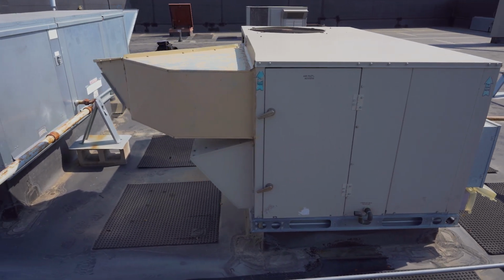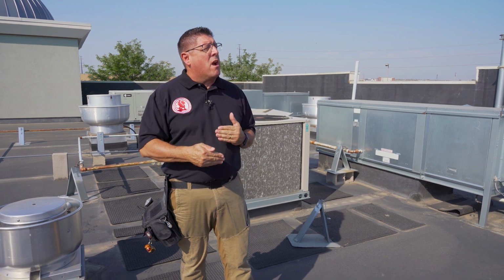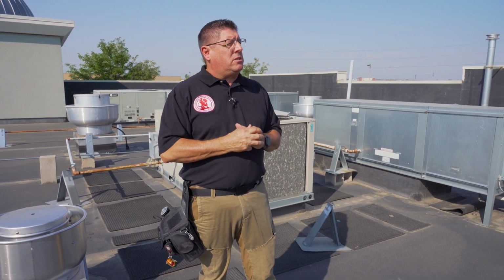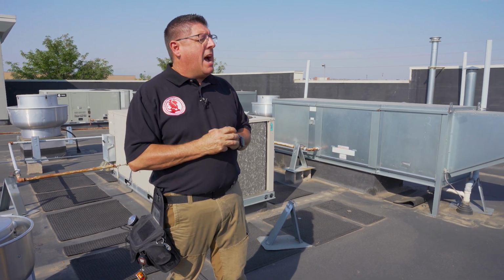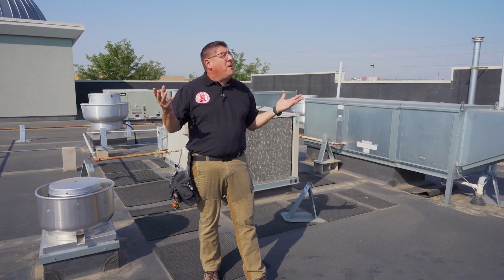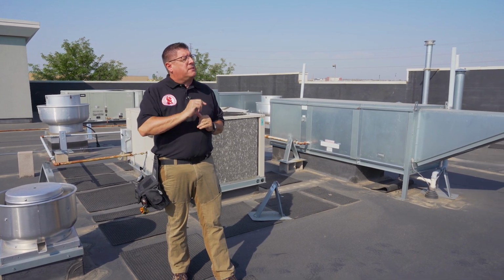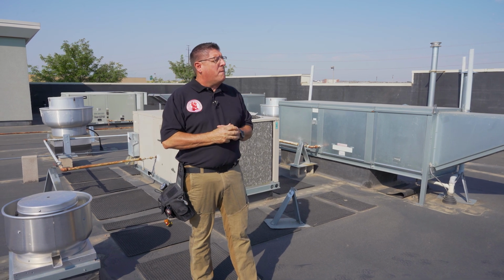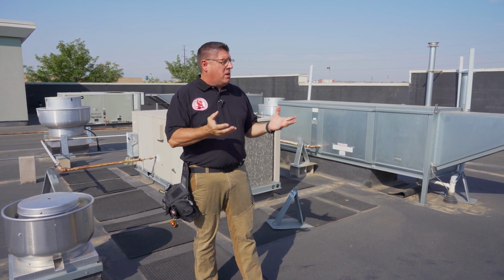These units up here on the roof are obviously not in a confined space, but it is very important when you do your inspections to note that if there are any units in a confined space, while we don't calculate for combustion air, we do need to be aware of the combustion air requirements necessary. Also, on all units, there should be a luminaire as well as a convenience receptacle. Now, in this particular unit, there's a convenience receptacle right on it, so we're in good shape, but it should be GFCI protected. As we do the inspection, we'll make sure that that operates. This is outside. We're up on the roof. A luminaire is not required here, but if it is in a closet or a confined space, we would expect to find some form of lighting in that room so that the technician or yourself can work in light and not have to have artificial light provided.